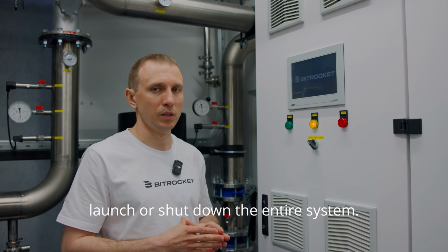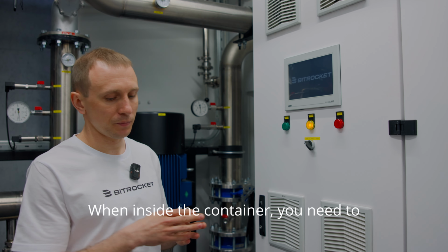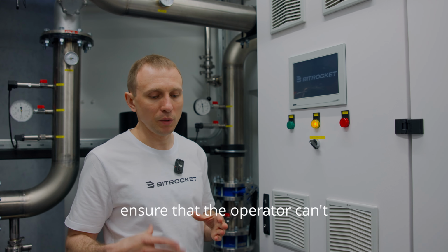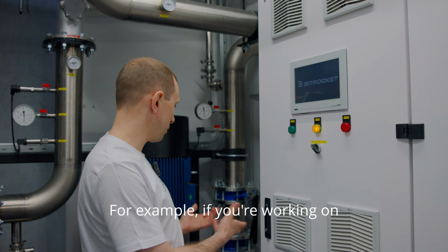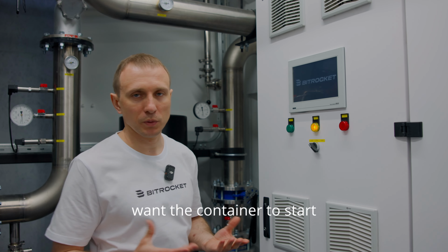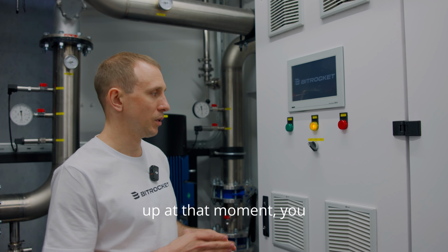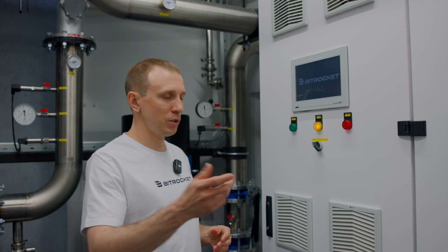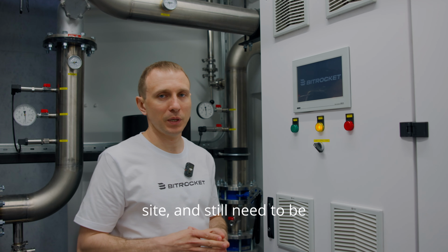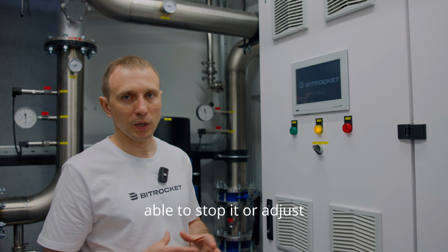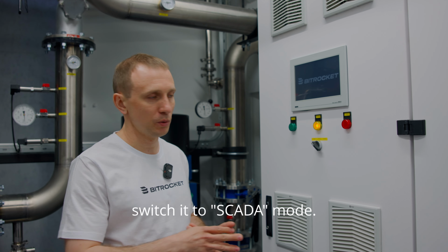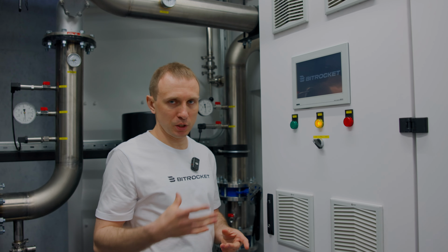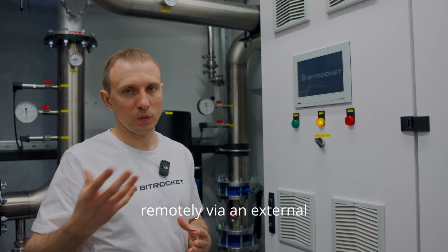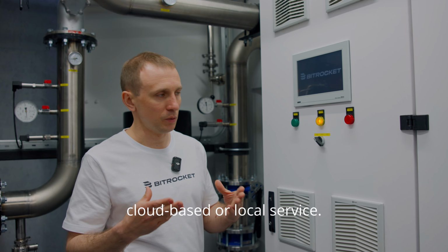down the entire system. When inside the container, you need to ensure that the operator can't accidentally interfere with the system. For example, if you're working on something and you don't want the container to start up at that moment, you switch it to local mode. If you started the container, left the site, and still need to be able to stop it or adjust some parameters, you switch it to SCADA mode. And then the container can be controlled remotely via an external cloud-based or local service.